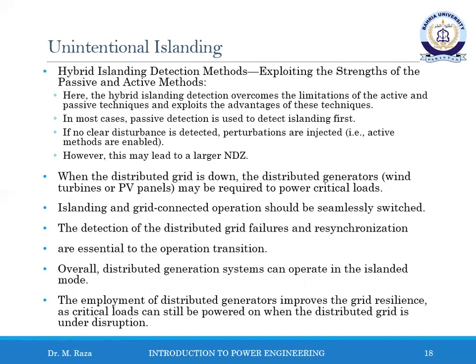When the distribution grid is down, the distributed generators such as wind turbines or PV panels may be required to power critical loads. Further requirements include that the islanding and grid-connected operations should be seamlessly switched. Also, the detection of the distribution grid failures and resynchronization are essential to the operational transition. In short, distributed generation systems should be able to operate in the islanding mode. The employment of distributed generators improves the grid resilience, as critical loads can still be powered on when the distribution grid is under disruption.